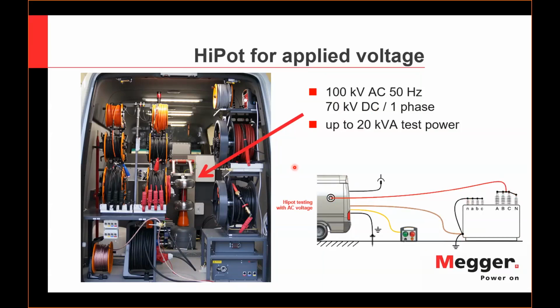So a typical application for the HiPot is that you apply a 50 Hertz test stress for 1 minute, and you see if the test passed. Basically, if you've seen no collapse of the voltage on terminals, it means that the test passed. Sometimes you can also connect a quadrupole and the PD test set and record any PD emissions to see that not only the voltage has not collapsed, but also if there are any PD at an early stage already happening in this insulation.